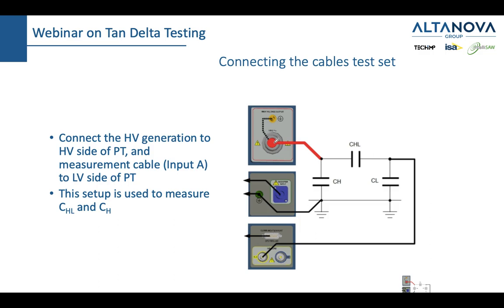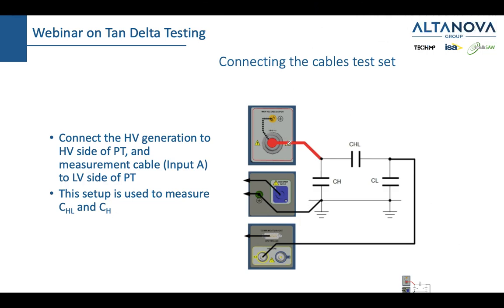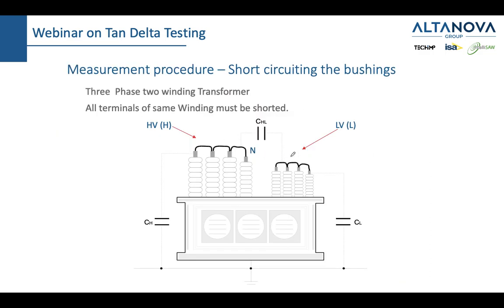So our first step in this case will be simply to generate first on the high voltage side and measure from the low voltage side. And just to remind you, this is the equivalent scheme of a two-winding transformer, because we have short-circuited all phases. We didn't short-circuit primary together with secondary, we short-circuited separately primary and separately secondary. And also, the neutral is also taken into consideration when we did the short-circuit.